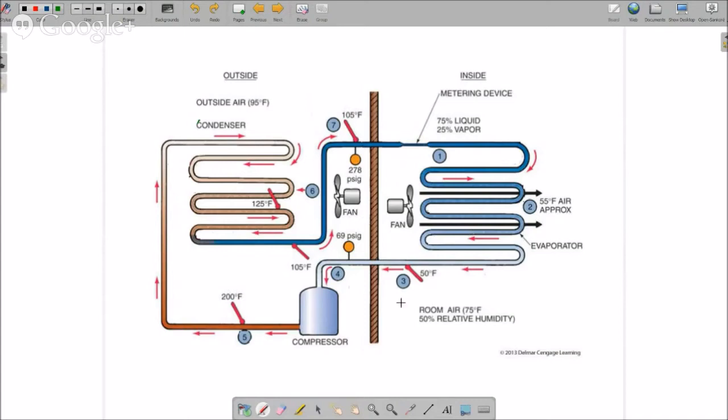And let's take a look at where we're at here with the pressure, or the temperature, in the evaporator coil. So here's our gauge over here. So we have, again, we've dropped pressure and we have a temperature drop as well. So here is our suction line gauge, and just like our condenser, when you hook up your suction line gauge outside, you are really looking at what's happening in the middle of this evaporator coil. All right, you're not looking at what's happening right here, you're looking at what's happening right there.